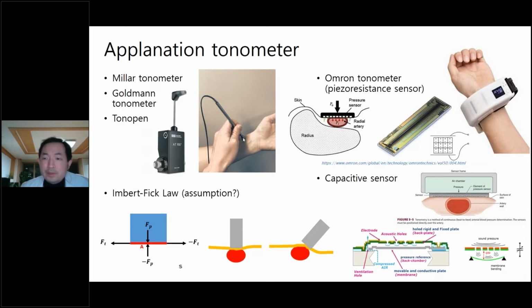Similar principle-based devices are provided by the Omron tonometer these days. They are under investigation. There are small plunger-like structures inside this device, and according to the pressure inside the artery, the flattened area of the artery provided by the pressure of this small group of plungers will be proportional to the pressure inside the arteries.